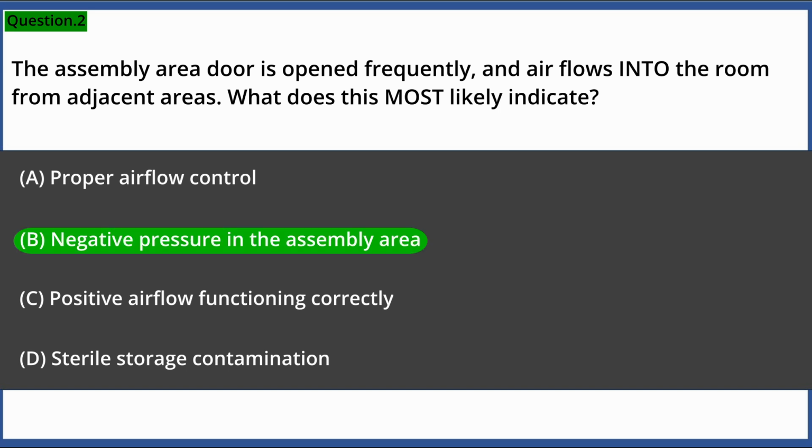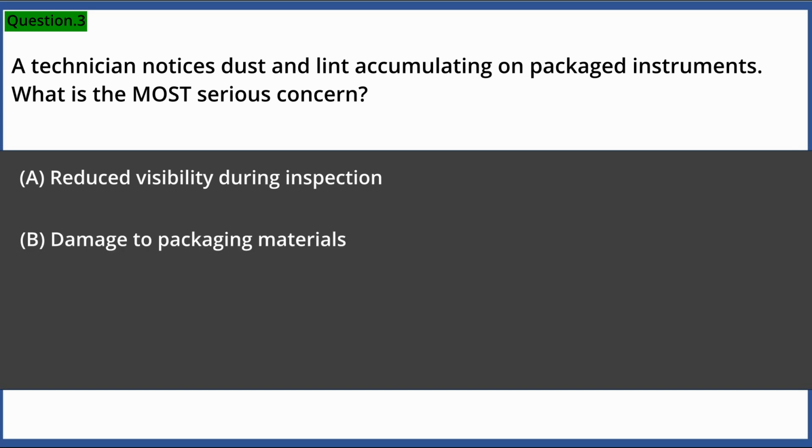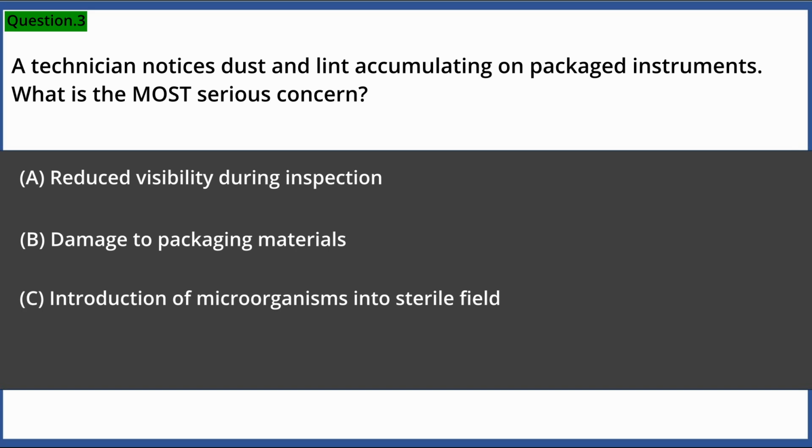Answer: B. Negative pressure in the assembly area. A technician notices dust and lint accumulating on packaged instruments. What is the most serious concern? A. Reduced visibility during inspection. B. Damage to packaging materials. C. Introduction of microorganisms into sterile field. D. Increased cleaning time.